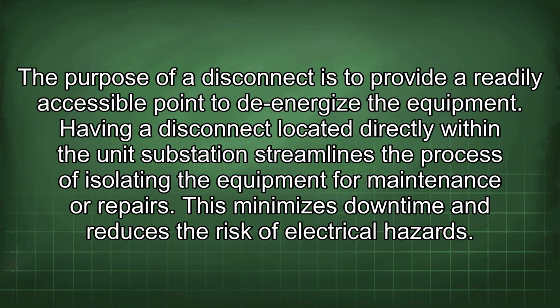The purpose of a disconnect is to provide a readily accessible point to de-energize the equipment. Having a disconnect located directly within the unit substation streamlines the process of isolating the equipment for maintenance or repairs. This minimizes downtime and reduces the risk of electrical hazards.